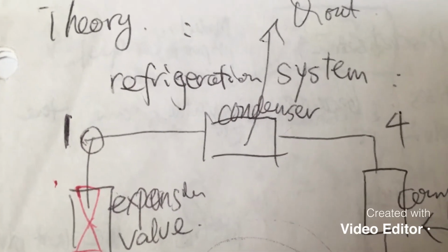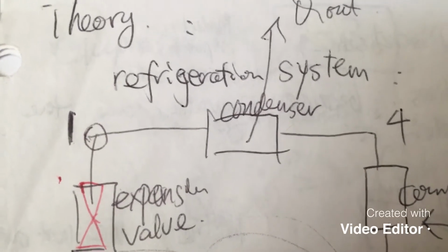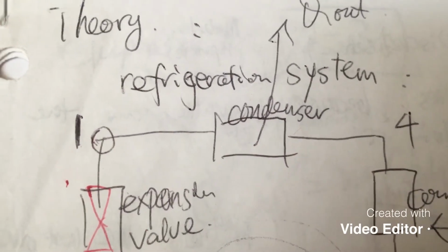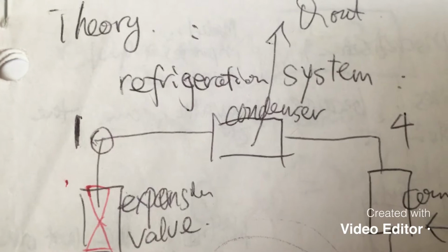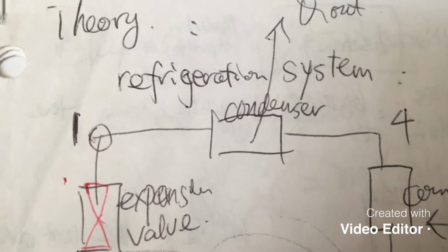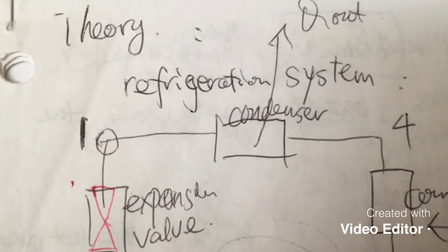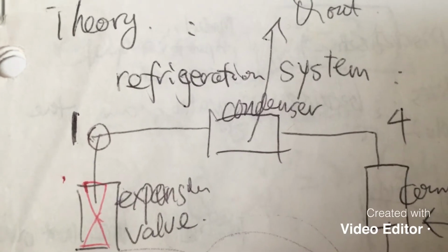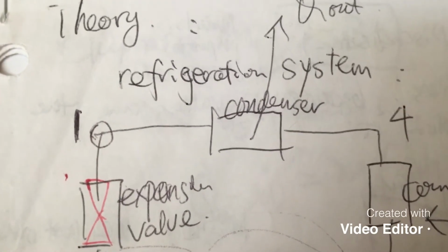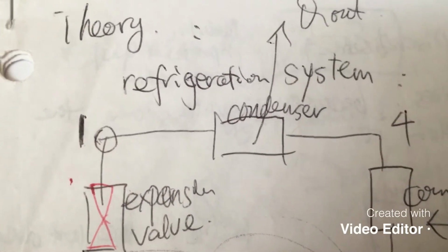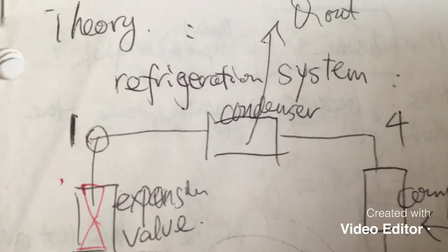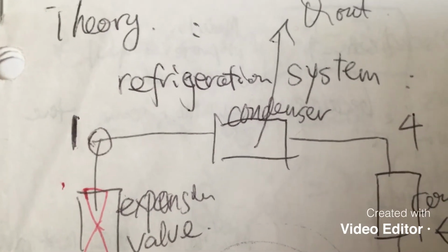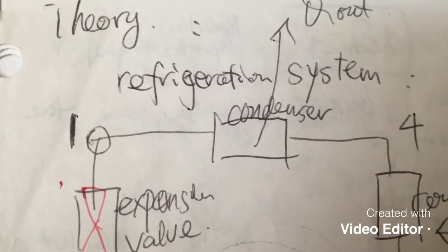That will be equal to the heat loss in the refrigerant side. In the refrigerant side, m dot delta H. Delta H, you can measure it. So in that sense, you can calculate the mass flow rate of the refrigerant. For the measurement, you need to measure at the same time because you are looking at equilibrium. So in reality, one student maybe measures the refrigerant side, one student measures the water side temperatures at the same time, so you can reach a better measurement because it's an equilibrium. So you better measure at the same time.